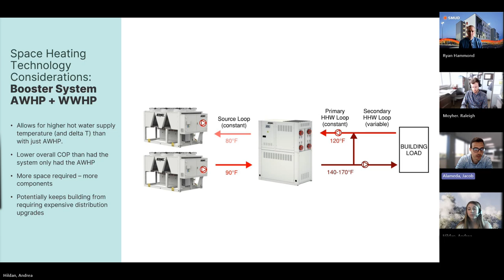So this solution obviously does cost you some overall efficiency because there are multiple stages of heat pumps operating, but it can help owners avoid changing out existing piping and coils in their building, which can be a huge cost saver. So there's a cost of going with this type of system. You pay upfront for the additional equipment. It's a little bit more complicated. You sacrifice some efficiency because you're running more equipment, but it does have the value of reusing your building's existing heating water piping and heating water coils, which could be very significant value depending on the application.